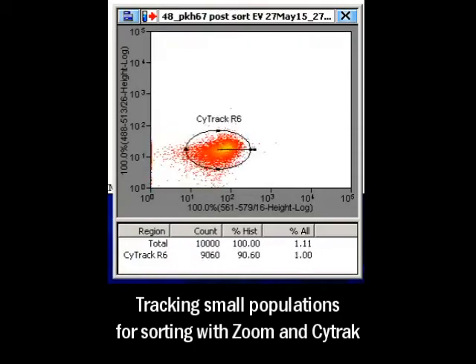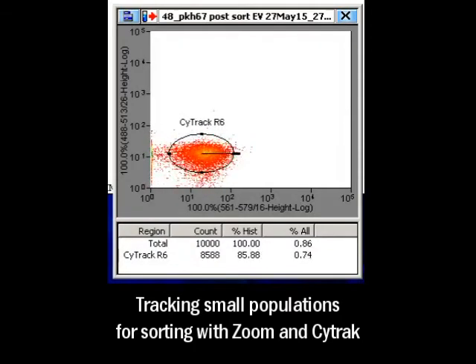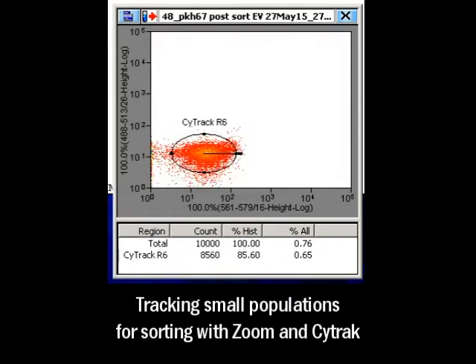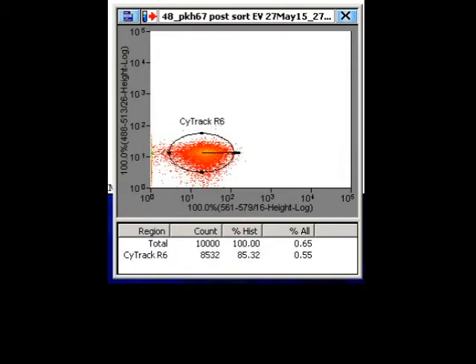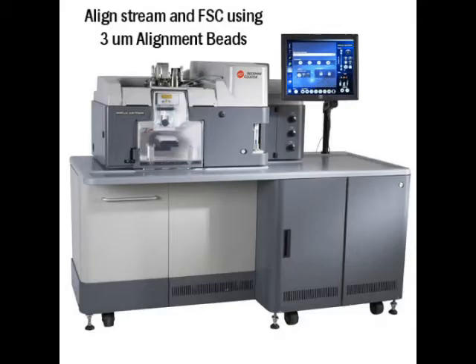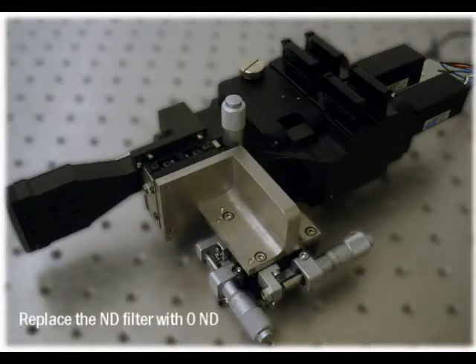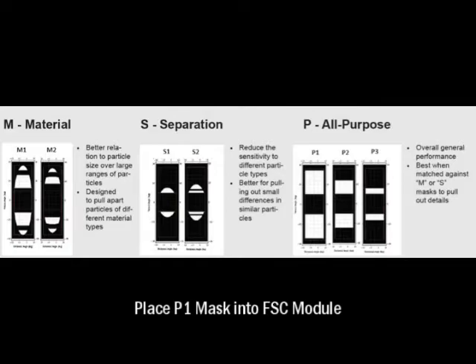The next video demonstrates Cytrak with Zoom, a complementary feature of Summit for the small particle sorting of distinct populations. Setting up the MoFlo Astrios EQ for less than 1 micron particle detection. First, align the stream and the forward scatter with 3 micron alignment beads. Replace the ND filter with a 0 ND filter. Change the mask to P1.